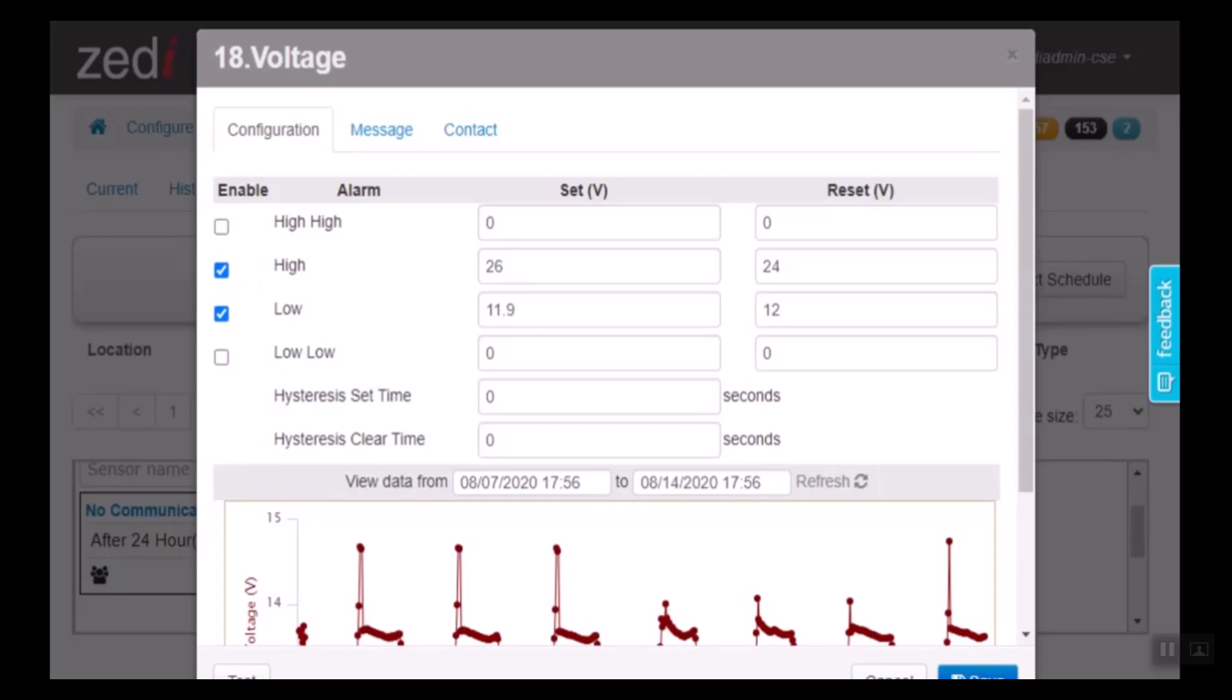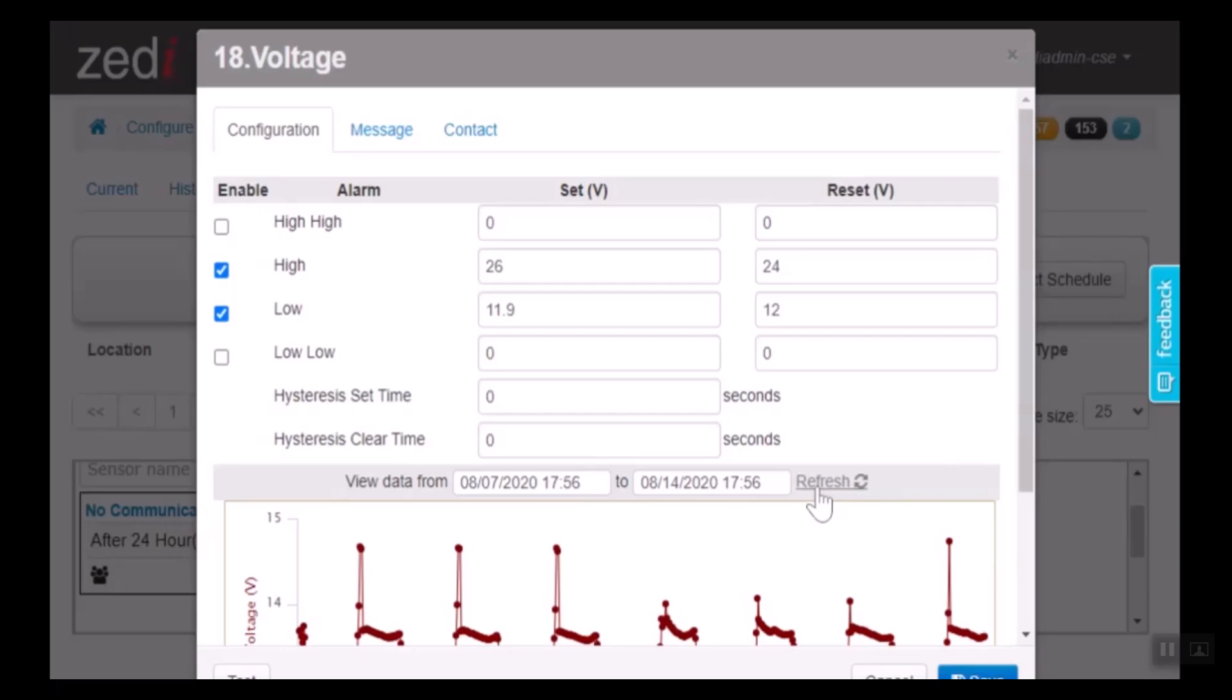You can set the reset time, the reset value, and you can select the hysteresis time. After a certain amount of time, the RTU will run a demand poll and confirm whether the sensor is in the alarm state or if the alarm can be cleared.